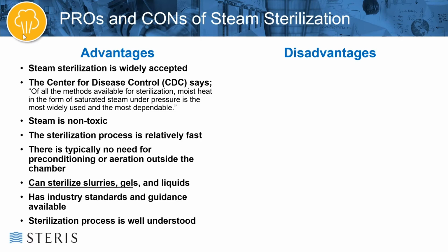So of these advantages, I think one of the most important ones is the fact that you can sterilize liquids, gels, slurries, types of products using steam sterilization that you simply cannot sterilize in ethylene oxide, and you can rarely sterilize with radiation because quite often the radiation will cause problems with the actual liquid or gel or the slurry with cross-linking and polymerization and various other things. So it's important to realize that this is probably one of the key advantages to steam sterilization.